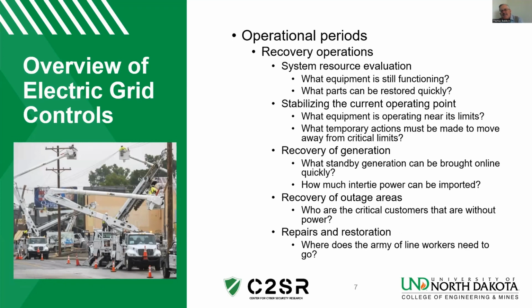The recovery after an event is important just as well. And this is where humans really come into the loop. System restoration and identifying key resources that are still available, what can be put back into service quickly, how to stabilize the system, where are we reaching limits that might create cascading events, what actions need to be taken quickly to bring the system into a more stable operating point, how do we get equipment back online, restoration of generation, recovery of generation, bring it back online if possible, minimizing the outage area, and over time making the repairs in the outage area and restoring power back. Some of this is automated, a lot of this is human in the loop, and so recovery is an important piece of the puzzle.